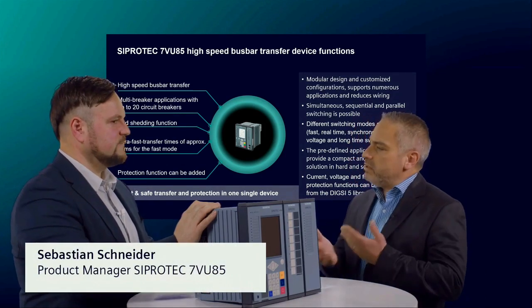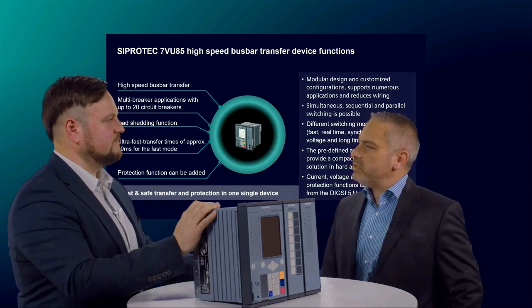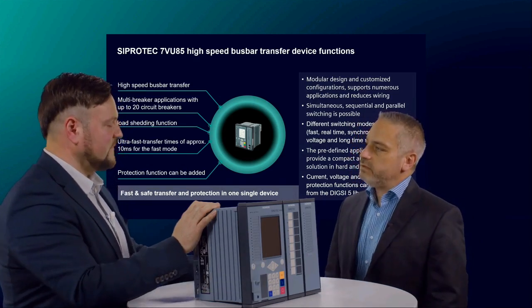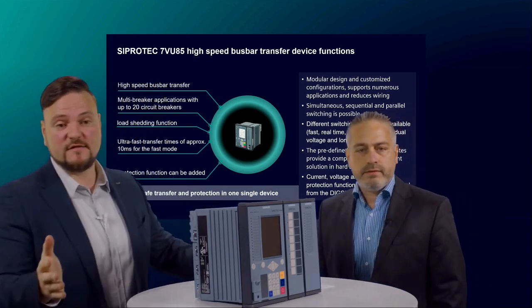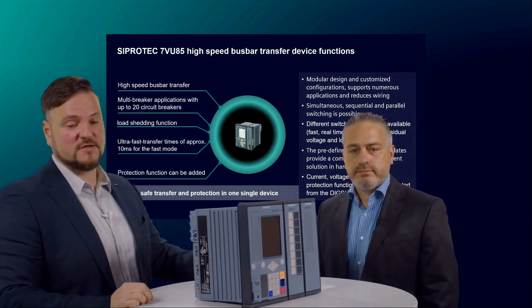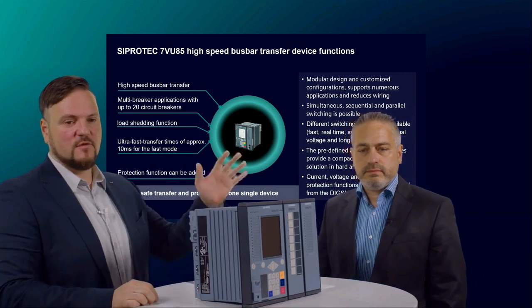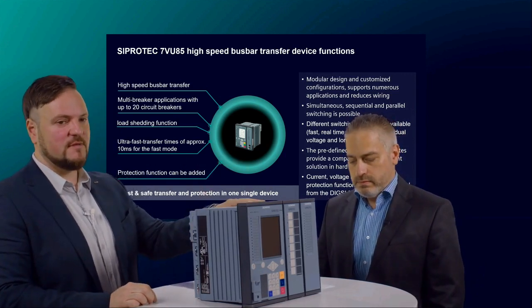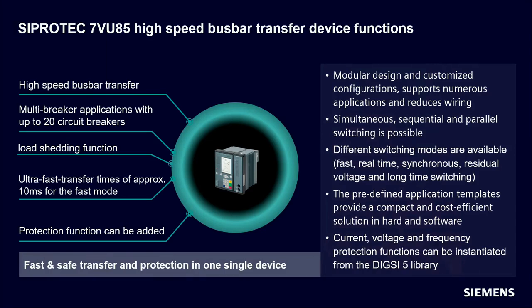Very interesting. But can you also tell us something about the functions and highlights of the new 7VU85? Yes, of course. If you have a look here on the slides, you can see the device functions of this new device type. So mainly we have the HSBT function implemented on the SIPROTEC 5 platform. We can support up to 20 circuit breakers. We have the automatic load shedding functionality implemented. Then we have the new ultra-fast transfer times of approximately 10 milliseconds for the fast mode.